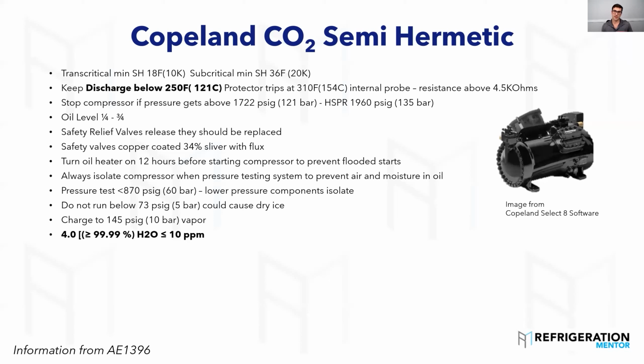Here's one of the little differences. So this is Copeland grade 4. So you see in Bitzer was 4.5 and 4.5, which was less than 5 parts per million. They say less than 10 parts per million in their guide. Once again, doesn't matter what either one of them say, you need to make sure that refrigerant's going in dry. So if you have to use a filter to go before. Recommend charging through a filter dryer. Both manufacturers do recommend that. Keep that refrigerant dry.